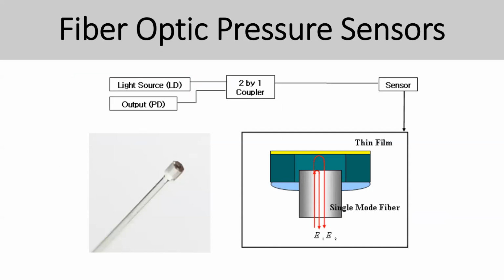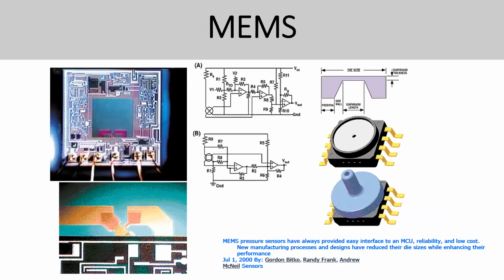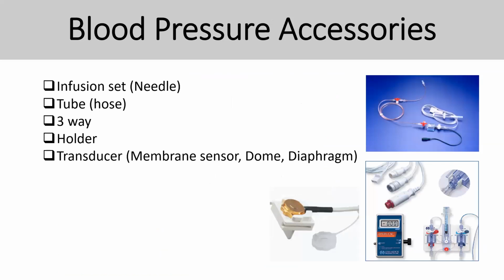This is one of the fiber optic pressure sensors. This is one of the types that they can use to measure the pressure. And the more accurate one is MEMS, micro-electromechanical system, which is more accurate and high quality pressure measurement. So this depends on the patient monitor that you're going to see. Sometimes they're going to use this as one of the important parts. So these are the blood pressure accessories for IBP. Normally what you need is an infusion set, tube, three-way connector, holder, and transducer, membrane sensor, and dome diaphragm. These are some of the common accessories used in IBP.